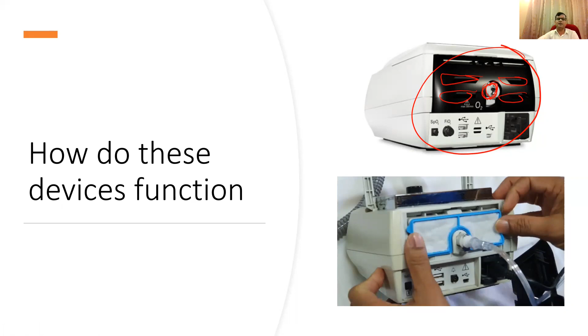If you look inside, you can see the bulk of the device is occupied by a blower, which blows air into the patient. This is where we connect the single limb, which connects to the patient. Air is entrained into the blower, and the blower uses a motor to generate pressurized air at whatever pressure you have set. So this is basically designed to work on room air, and oxygen is an optional thing. This is how these devices function in a domestic environment.